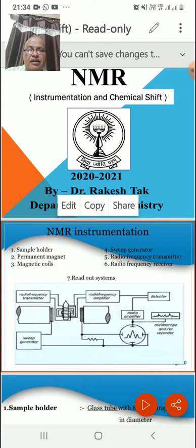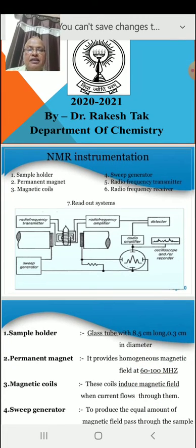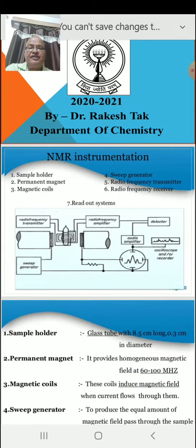NMR instrumentation has six or seven parts: the sample holder, the permanent magnet, magnetic coils, sweep generator, radio frequency transmitter, radio frequency receiver, and the readout system. The instrument is composed of these seven things.